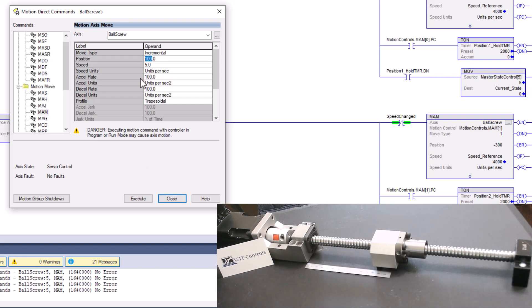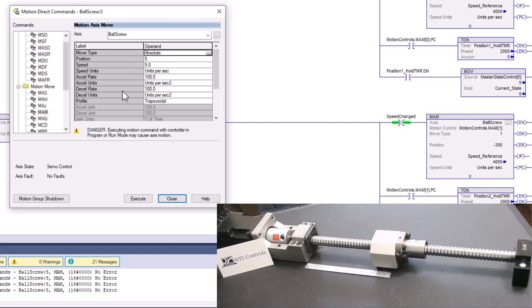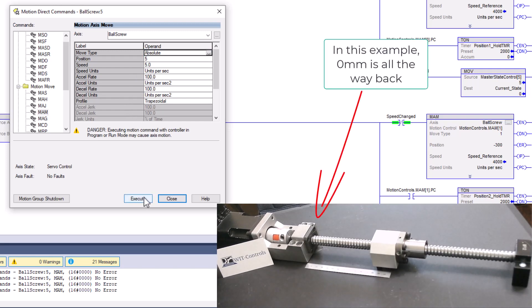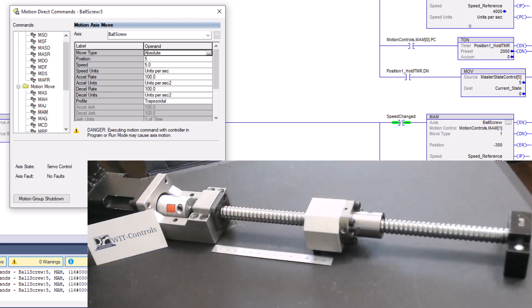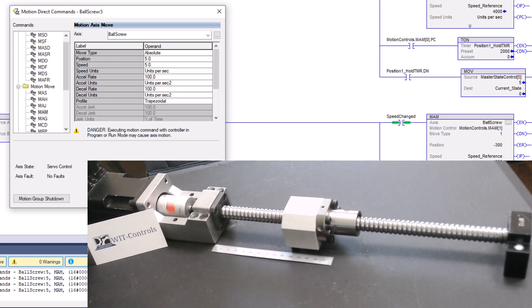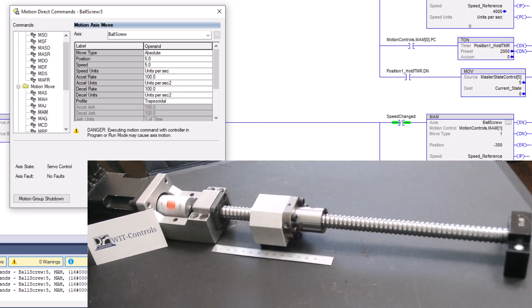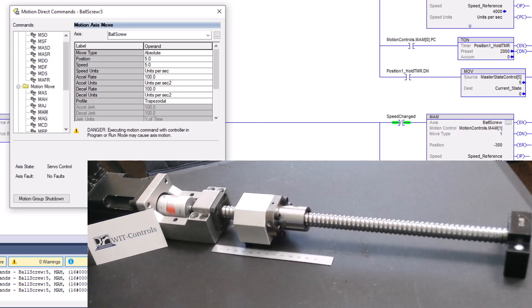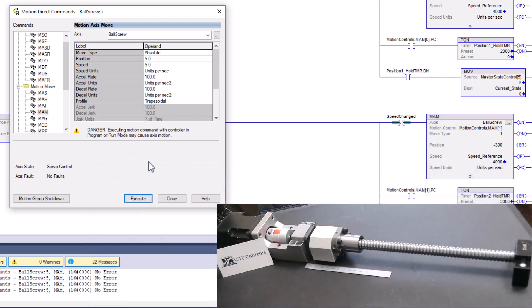So if we wanted to go back, again, to our set point or let's just say we wanted to go to zero, let me put it this way. Let me put it at five and let me go to absolute and show you what that does. Because if I go to a position of five, it knows right now it's homed all the way with the block against that. So when the block is completely against the actual frame or what the servo mounts to, what it is is basically zero. So if I put five it's going to be really close. So if I do an absolute move, it's going to move that block to that position that servo knows. So if I had already not homed the servo, I could have actually caused some damage or I could have tripped my servo out. So in this case it's going to go to five millimeters and then it will stop. At that point you see it does stop right before the block, the end of the block, and that way you can easily see that.